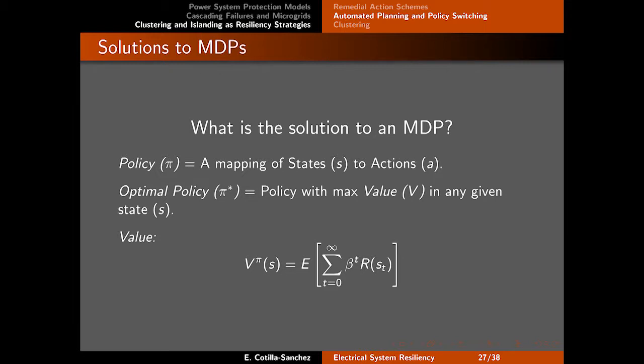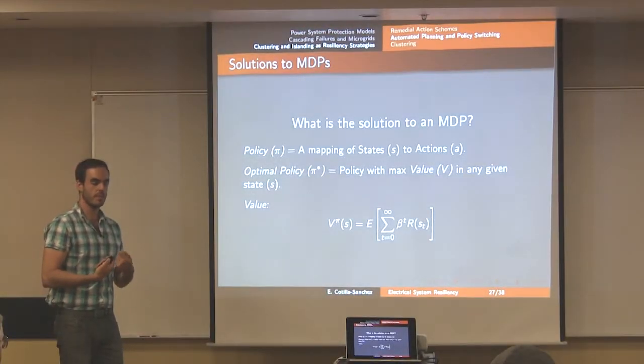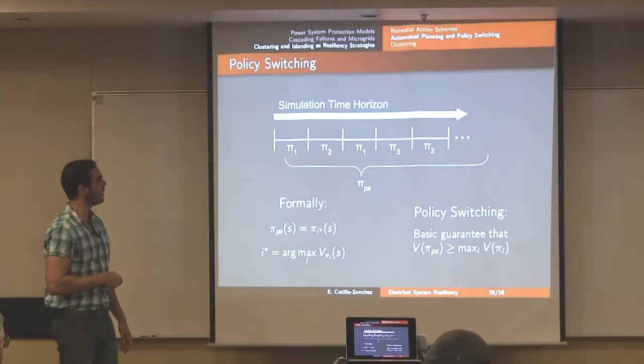So there's a policy that basically, if I say the reward, I can measure a reward like we did at the beginning of the presentation and say percentage of loads that I'm still serving, that's going to be the reward from my computer calculation. So the larger that number is, if I want to put it in per unit from 0 to 1, 1 will mean that all my load is being served. 0 will be a complete outage. So I can play with that reward number to try to calculate the risk essentially of taking those actions as a way of doing a heuristic control.